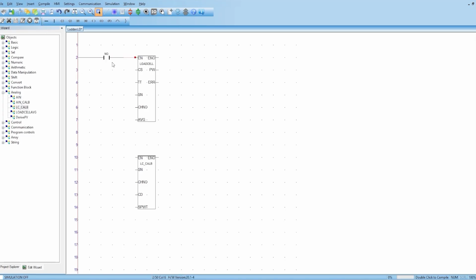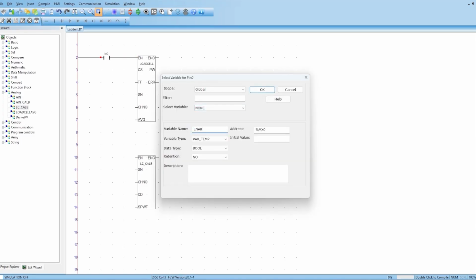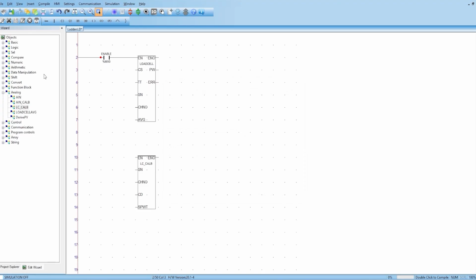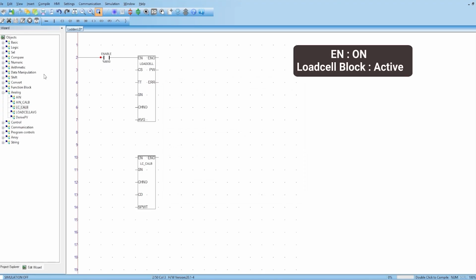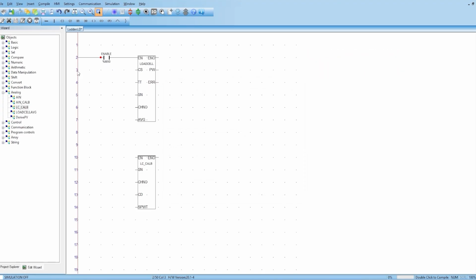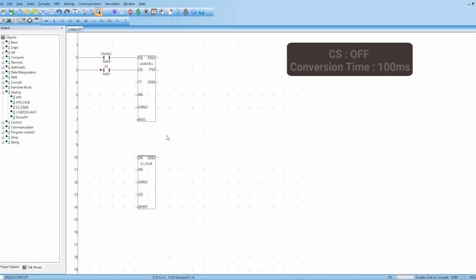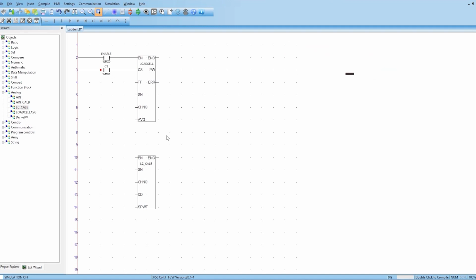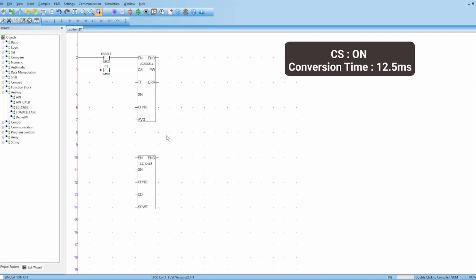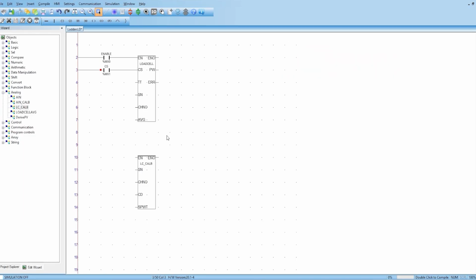Within the Load Cell block, the EN input is used to enable the operation. When EN is on, the Load Cell block becomes active. The CS input stands for conversion speed. When CS is 0, off, the conversion time is 100 milliseconds. When CS is 1, on, it's reduced to 12.5 milliseconds. This setting lets you select between standard and high-speed conversion, depending on your application requirements.